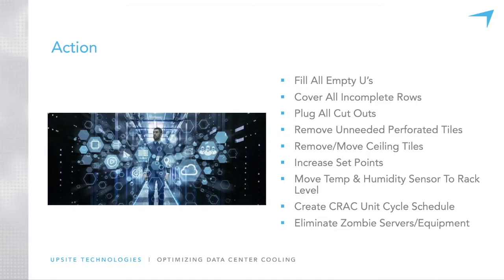However, because of all these openings and inefficiencies and poor airflow management, it's quite common for only about half of that cooling capacity to actually be utilized. The other half is stranded capacity wasted in the form of bypass airflow. So just comparing that total installed rated cooling capacity to the UPS output load gives people a real quick indication of how well they're utilizing that installed capacity.